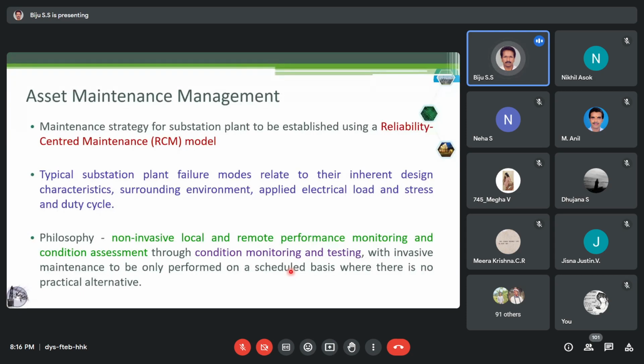Now, the philosophy of maintenance is like this: non-invasive local and remote performance monitoring and condition assessment through condition monitoring and testing. You will do online condition monitoring and online testing. And you will do invasive maintenance only if it is absolutely necessary and there is no practical alternative. So it brings down the outage time like anything.